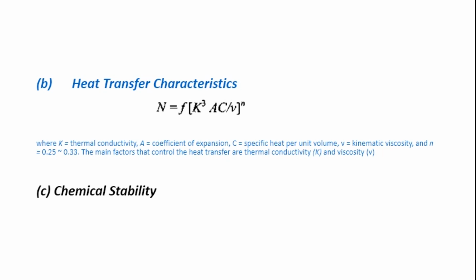This will increase the dielectric losses. Sometimes there is a formation of discharges and arcing between the two electrodes. If remedial action is not taken, this cycle continues, and the worsening of the liquid purity and of the equipment condition are the two things that add up to the chemical instability, resulting in a breakdown taking place between the two electrodes.